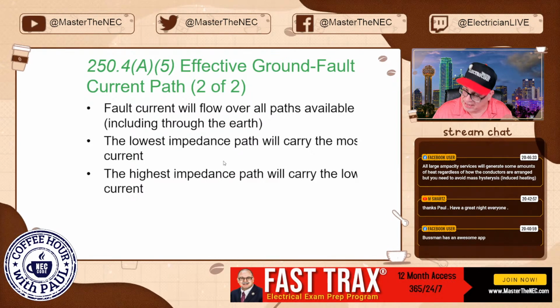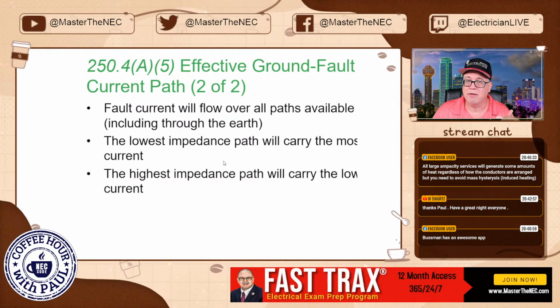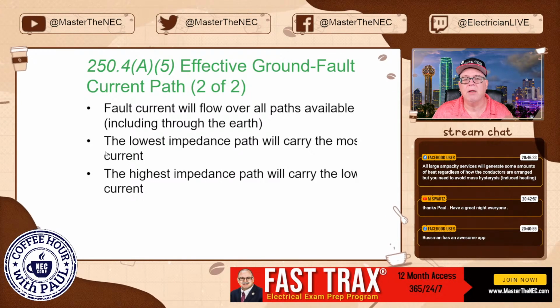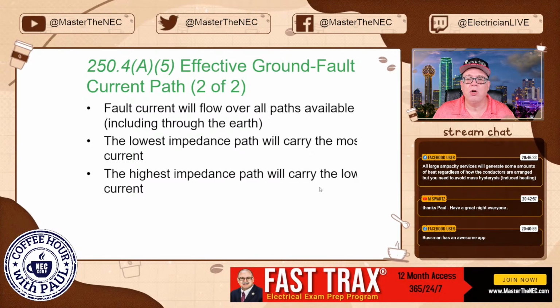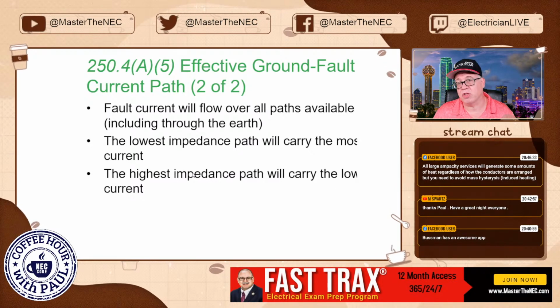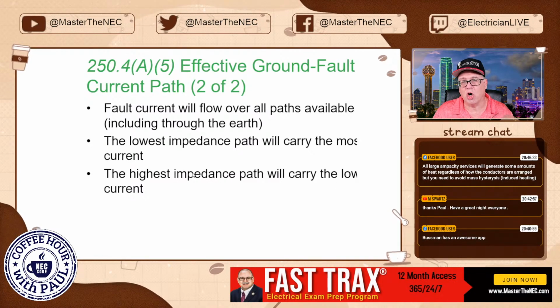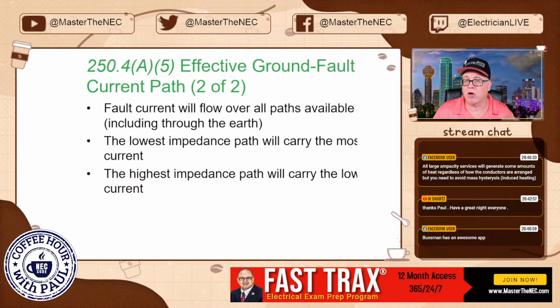And why is that important? Because that's what we're trying to clear a breaker. That's what we're trying to do, okay? The highest impedance path will obviously carry the lowest amount of current. So the earth, for example, if there was any traveling on earth, it's going to be low.